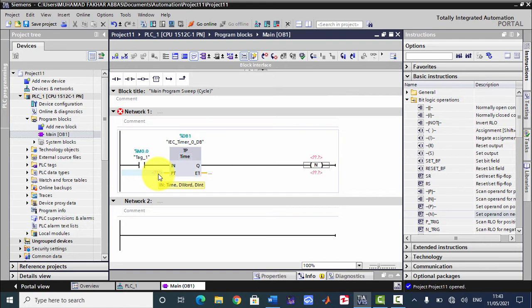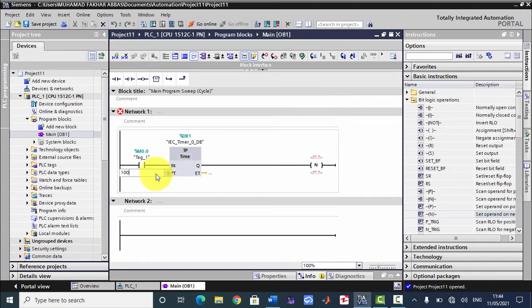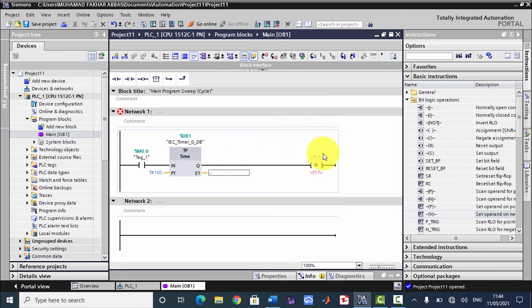Let's program this system. For the pulse timer, we will add the time for how long we want the output to remain on. The pulse timer will give a pulse for that duration, which we set in the PT value. PT takes time in milliseconds, so we use 10,000 here — meaning 10 seconds. The pulse timer will give us a 10-second pulse, keeping our output on for 10 seconds, then it will automatically turn off.